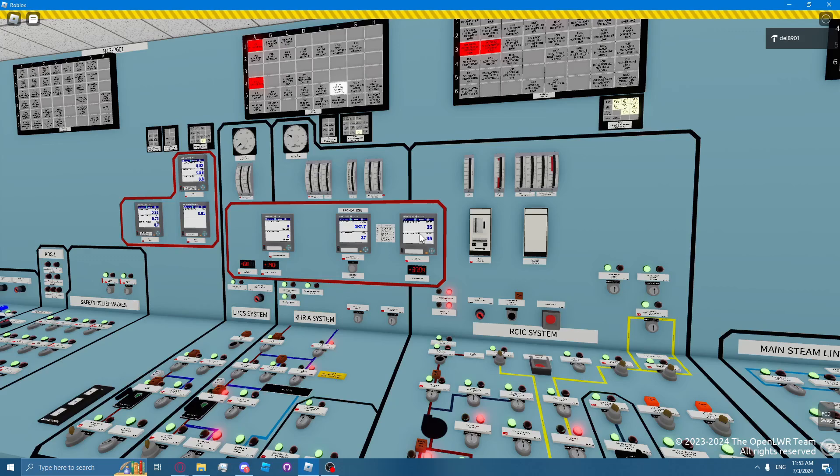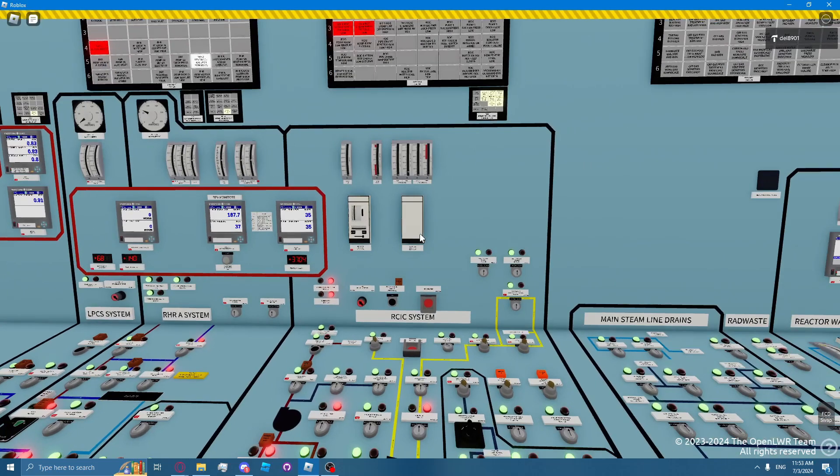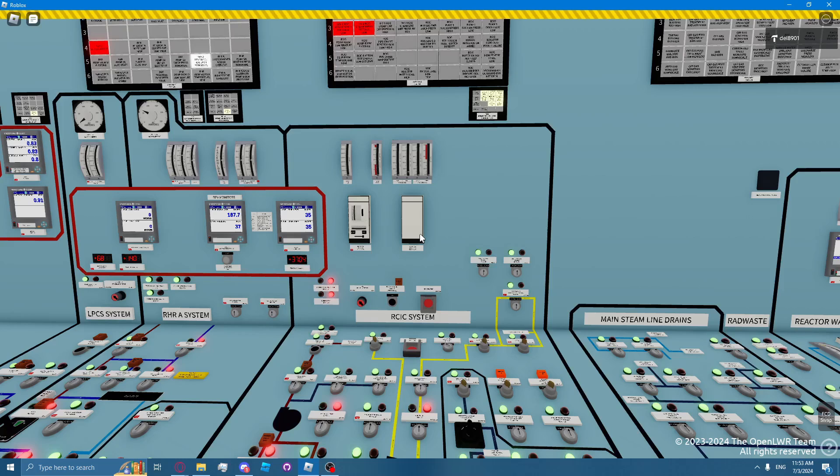The RCIC system also stops on reactor level 8 by closing RCIC valve 45. RCIC will automatically cycle between level 2 and level 8 during a transient with zero operator action.